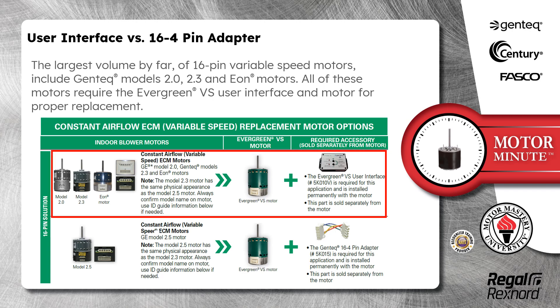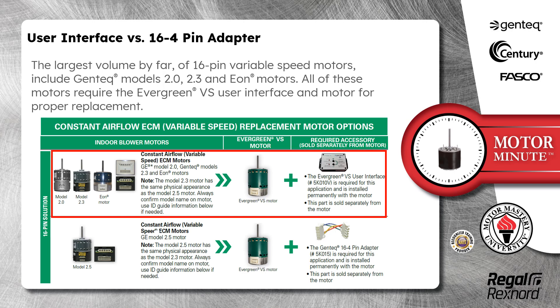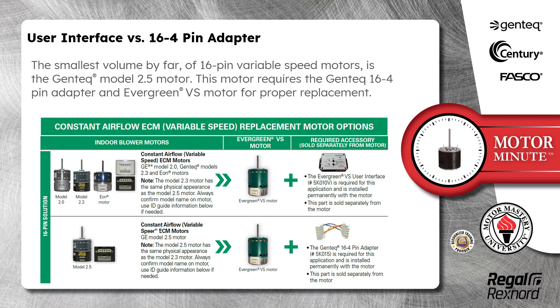All of these motors require the Evergreen VS User Interface and motor for proper replacement. The smallest volume, by far, of 16-pin variable speed motors is the Genteq Model 2.5 motor. This motor requires the Genteq 16-4-pin adapter and Evergreen VS motor for proper replacement.